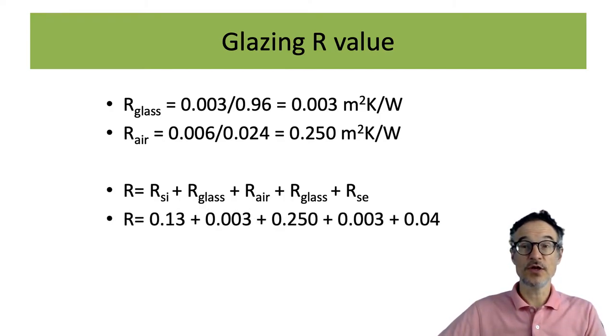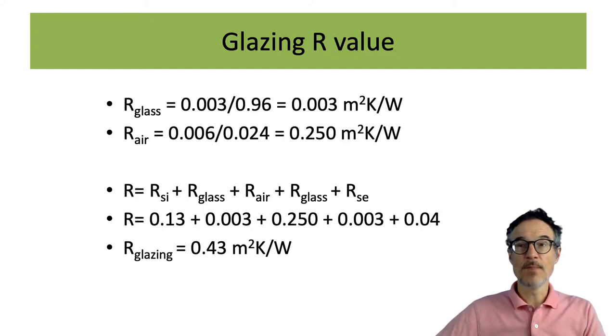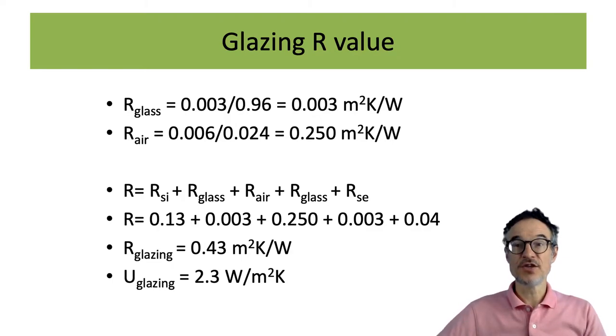And that's an R value for the glazing. That's fairly easy, just simple layers that we're adding up. So we're adding up the resistance. We can turn that into a U value, which comes to about 2.3.